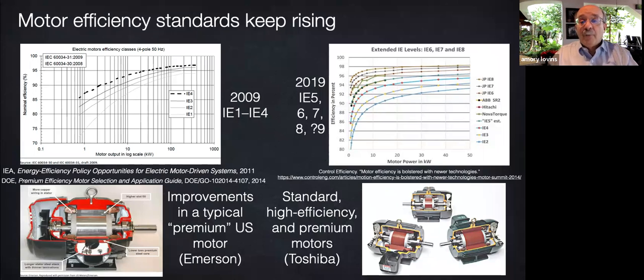Until then, 3/4 of a kilowatt to 1,000 kilowatts can be IE3. The US is stuck around IE2 for the moment, but all those old standards are becoming obsolete and woefully inadequate. Let's do it by the numbers. Some vendors already offer IE5. It's a bit better, especially at small sizes. You see in the upper right graph, and you see some up around the Japanese equivalent to IE6, 7, and 8, which do not actually exist yet as IEC standards. IE6 to 9 are emerging, as we'll see in a minute.